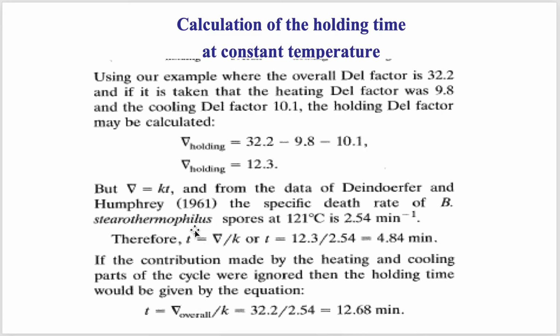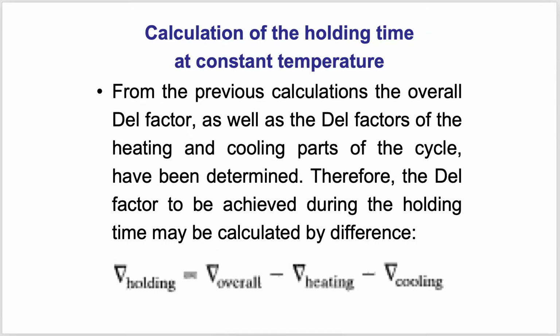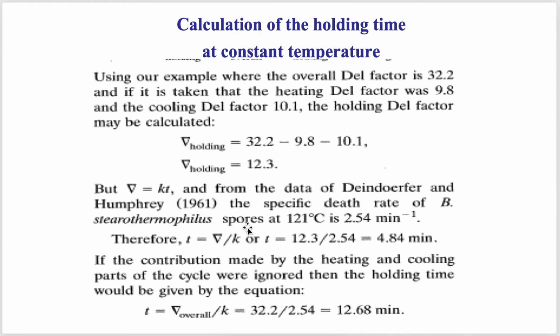In this way, by using the equations of the del factor, we can calculate the holding time for our batch sterilization process.